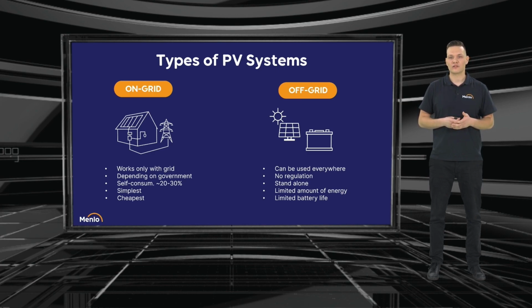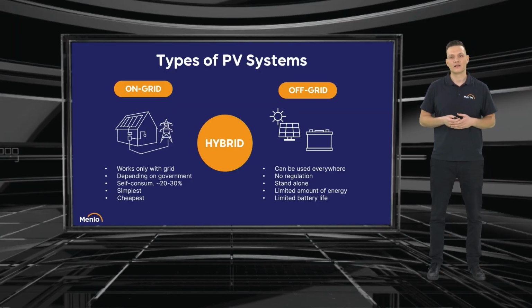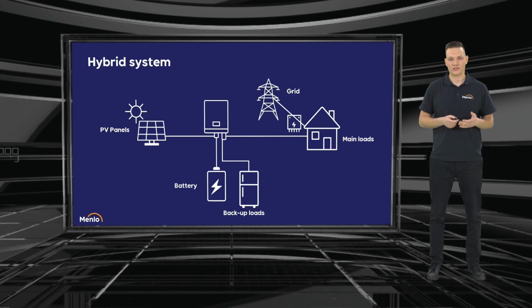The off-grid inverters can be used everywhere. There is no regulation. It's a standalone solution. So you can put it anywhere you want, and nobody will have a problem with that. The problem is that the off-grid inverter has a limited amount of energy and limited battery life. So it only runs if there is sun and if your battery is not empty. Then we have the hybrid system, which can combine these two solutions. So it can work on grid when we are connected to the grid, but when there is no energy in the grid, it can switch to off-grid mode. And when the grid comes back, it can work on grid as well. So it works in both of these modes.